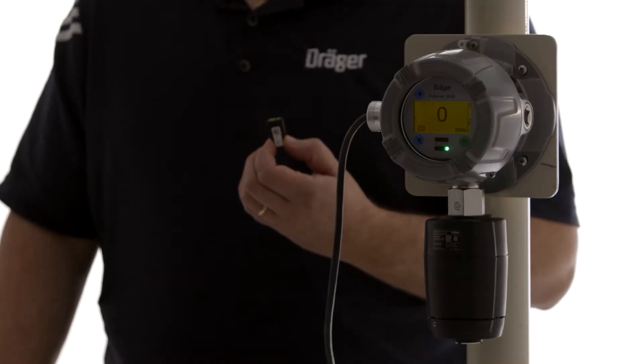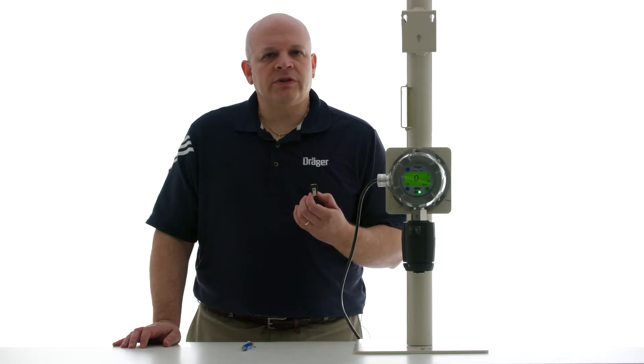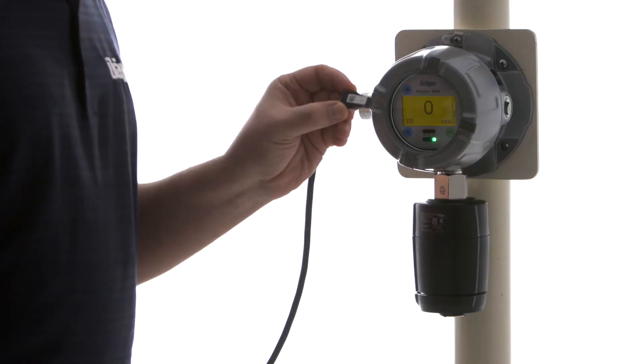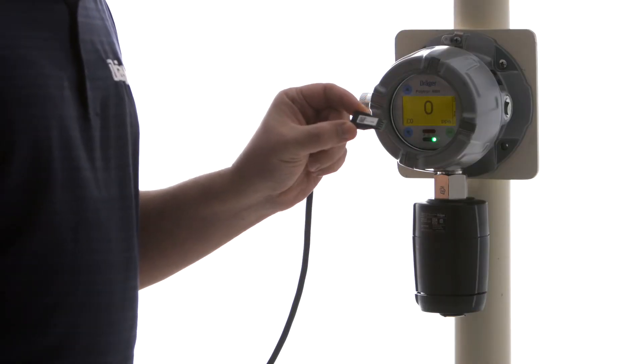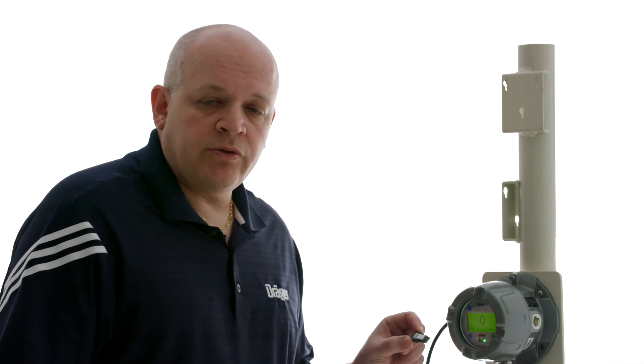I'm Steve from Draeger and today I'm going to show you how to install a diagnostic dongle into a Polytron 8100. The procedure is pretty much the same as it is for PointGard 2100. This diagnostic dongle will give us information as far as vitality and preventive maintenance, as well as perform some internal testing on the sensor as the device is powered on.